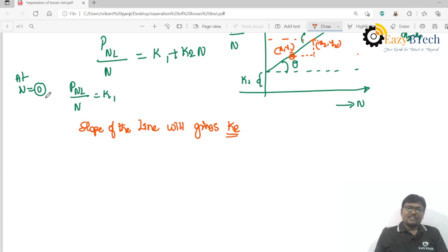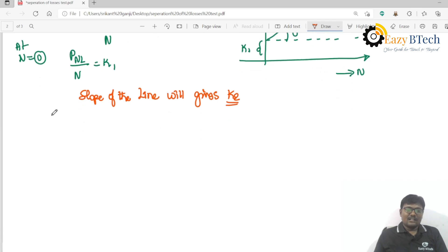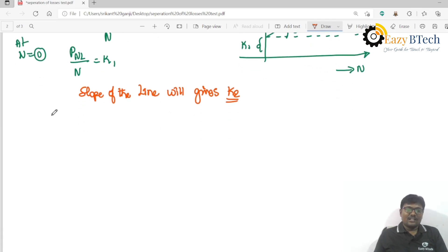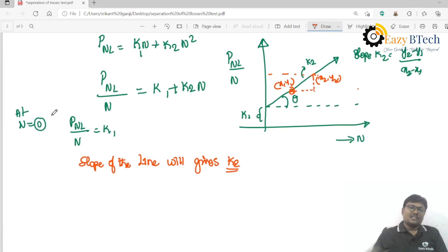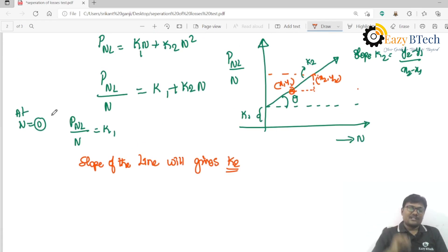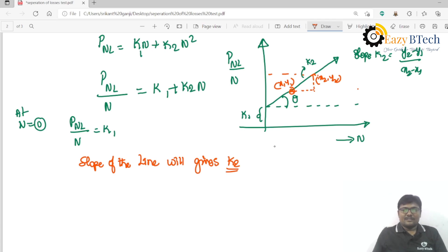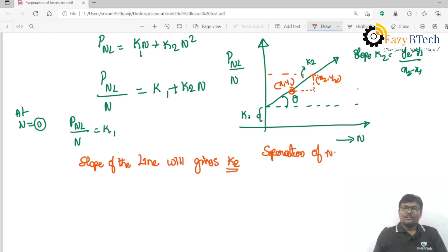This test is repeated for different values of field currents, and k1 and k2 values can be obtained for each. The graph shifts upwards for different excitations. This overall procedure is called the separation of no-load losses test.